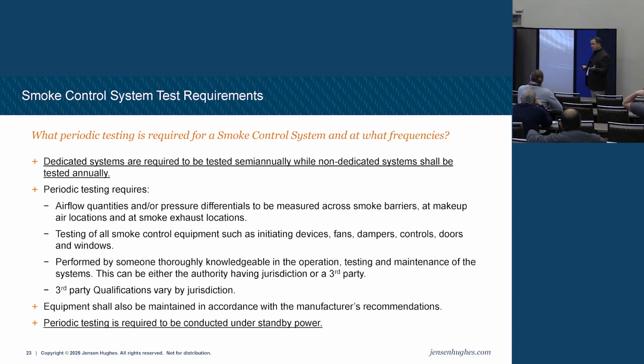And then if you're in a government building and you add in mass communication or anti-terrorism requirements, now you get into different messages during different events and all sorts of stuff. So it can get even more complicated. Equipment shall also be maintained in accordance with the manufacturer's recommendations. So it is possible that the manufacturer of a certain solenoid relay component will require, oh, this one needs to be actuated or exercised every week as part of that self-test. That would all be in the rational report, the design of your smoke control system. So that's why that original documentation is pretty critical.